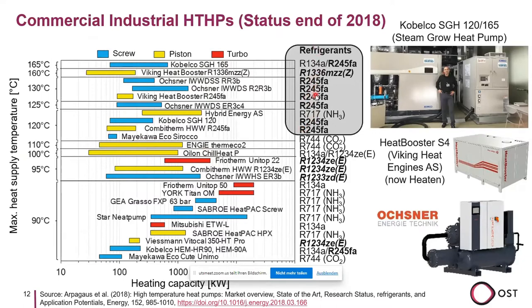And so the R245FA, which is a hydrofluorocarbon, needs to be replaced in the future because it has too high global warming potential. So there's activity in researching alternative fluids. Then there are the new natural refrigerants like CO2, ammonia, and water, and also hydrocarbons, which are counted to natural fluids.